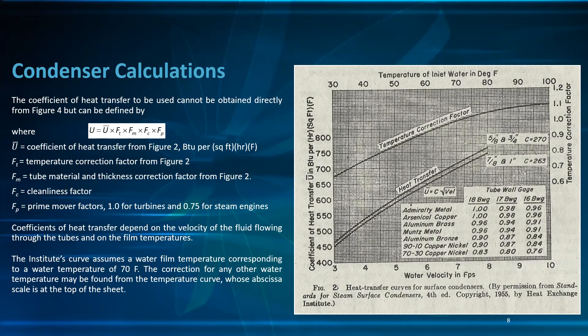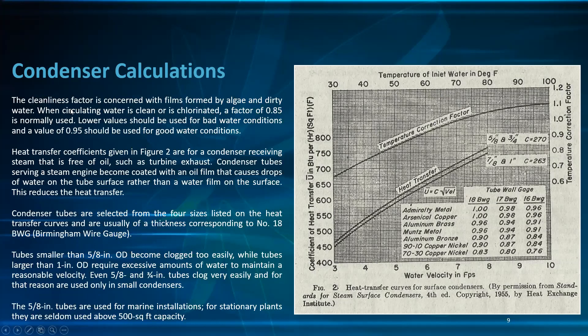When designing, refer to catalog codes rather than deriving values yourself, as the tables are already provided. The Institute curve assumes a water film temperature corresponding to a water temperature of 70°F; the correction for any other water temperature may be found from the temperature curve at the top of the sheet. The cleanliness factor F_C accounts for fouling by algae and dirty water: 0.85 for chlorinated water, lower values for bad water, and 0.95 for good water conditions.